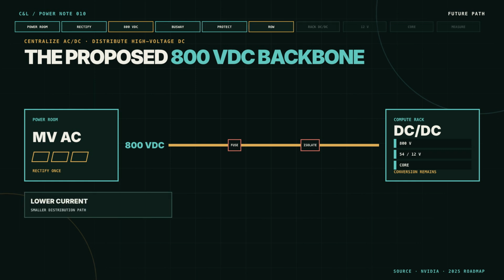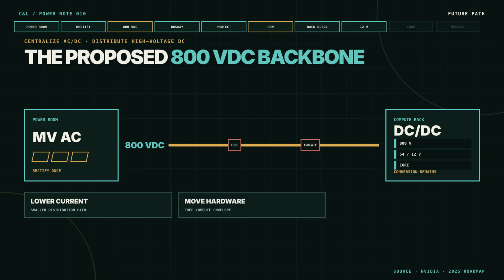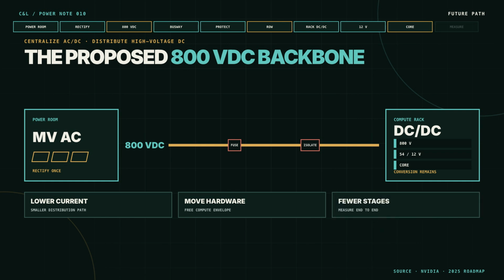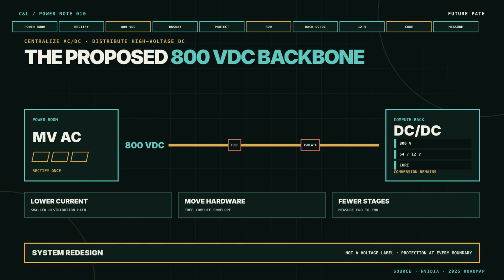Lower current can shrink the distribution path for the same power, while fewer rack power supply modules can free units for accelerators and cooling. The diagram also exposes new work. Every boundary needs overcurrent protection, isolation, and safe service. This is a system redesign, not a voltage label. Its value depends on the complete utility-to-processor chain at the actual load profile.